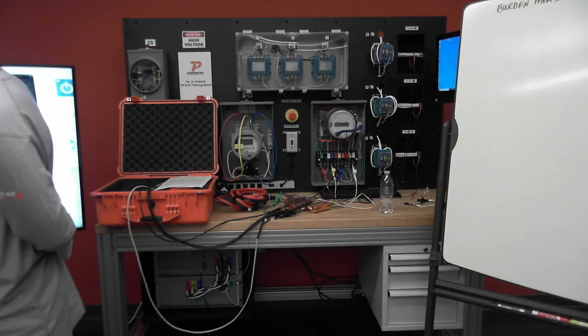It's showing right here, right? Because my ratio error is actually pretty small. Look, I tested 200.64 instead of 200.5. The other ratio is really good, okay? But it's this phase angle error on A phase.